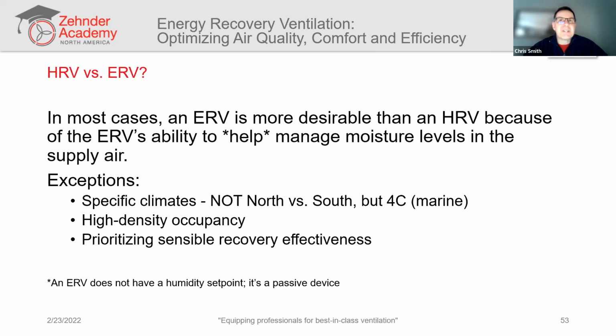Now, what are the exceptions? The exceptions are in specific climates, maybe an HRV is better. Let me debunk the north versus south conventional wisdom that's floated around for decades. It's not as simple as northern cold climates want HRVs and southern hot climates want ERVs. We've explained why a cold climate can benefit from an ERV. So really, it's more that specifically climate zone 4C, which is Pacific Northwest marine climate, that's the climate where an HRV is usually preferable over an ERV. In almost every other scenario, an ERV is preferable.